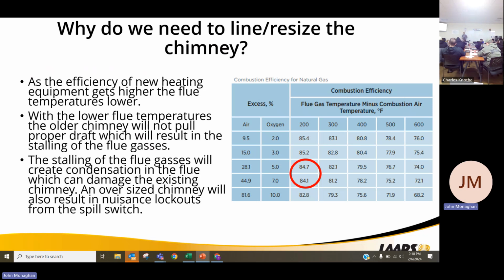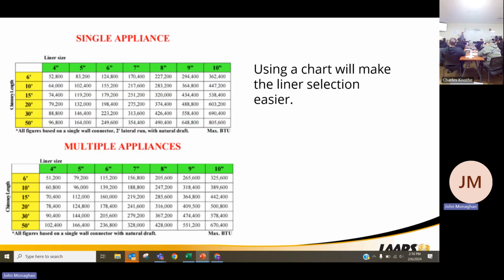You'll also get your flue gas stalling, which will cause your block vent switch to trip. I'm not pulling enough of a draft. I'm not heating it up enough. So you would look at your liner charts and how many BTUs I have, how high the chimney is, and what size liner I would need to drop down it. There are nicer ones out there than this chart here. This chart is non-discriminatory.